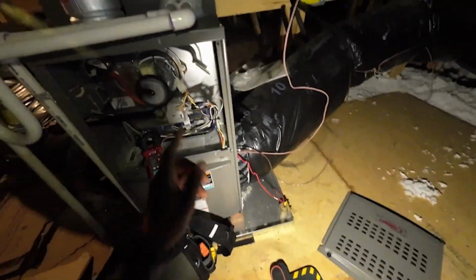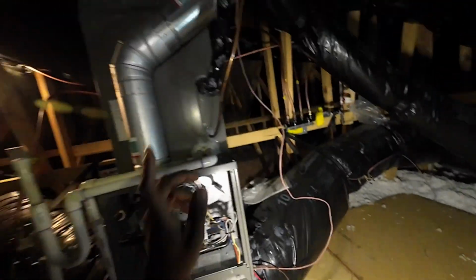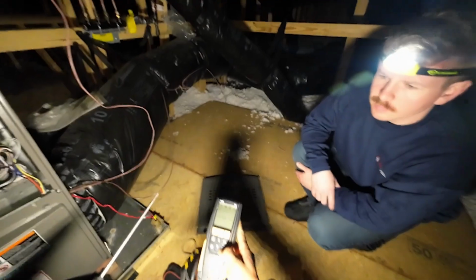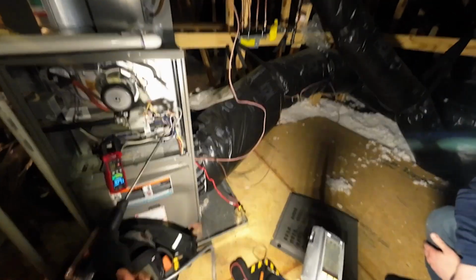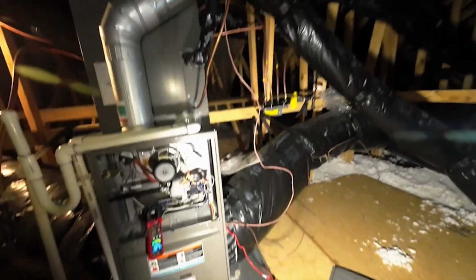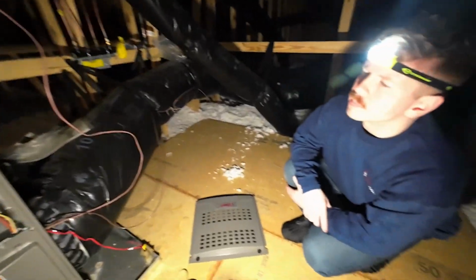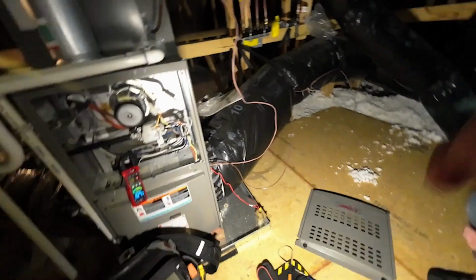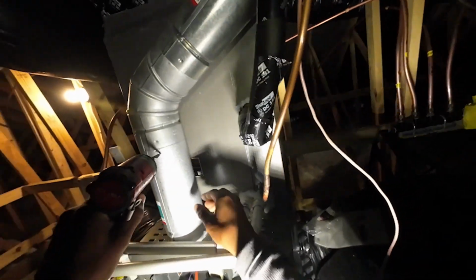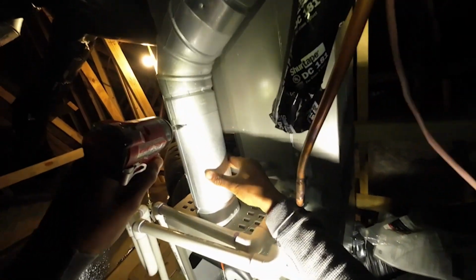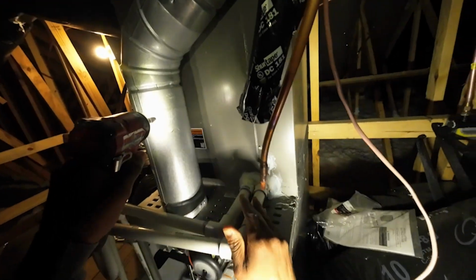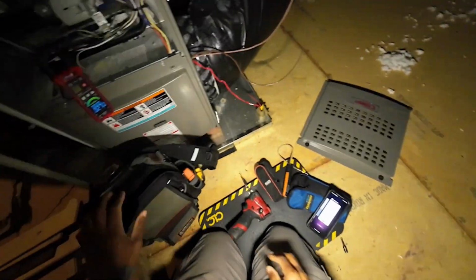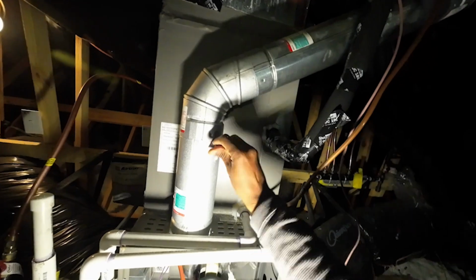We're still going to use this to check our gas pressure, but now I'm going to do a combustion analysis. This is a combustion analyzer. It's pretty much measuring, it's verifying that this is getting complete combustion, as complete as possible per the manufacturer's specification, that basically air and gases are mixing and creating a nice complete combustion. All right, so I'm going to go ahead and tap a hole here. You usually want to be about 12 inches from your, there she goes. Now we just take this thing, probe here.